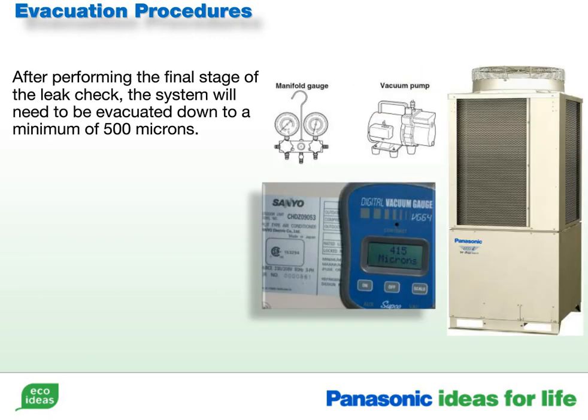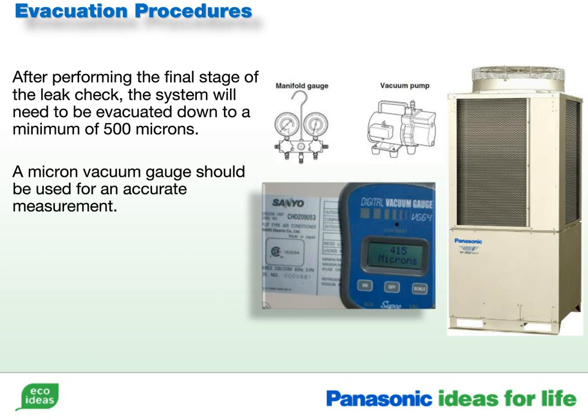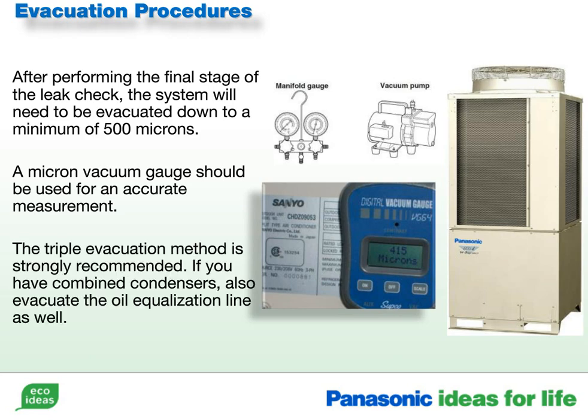Once you are sure that you do not have any leaks in the refrigerant lines, the system will need to be evacuated down to a minimum of 500 microns. A micron vacuum gauge should be used to ensure that you have an accurate measurement. The triple evacuation method is strongly recommended. If you have combined condensers, also evacuate the oil equalization line.